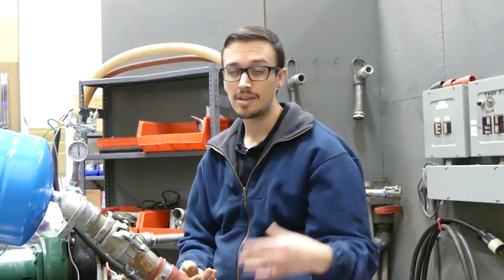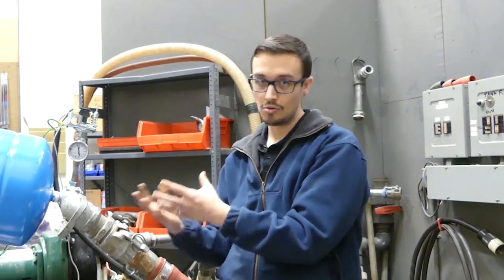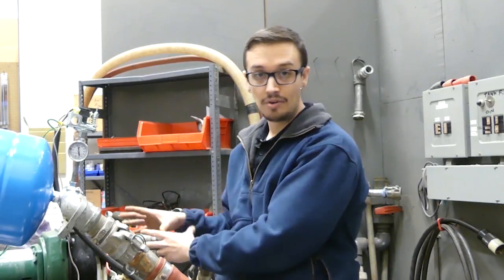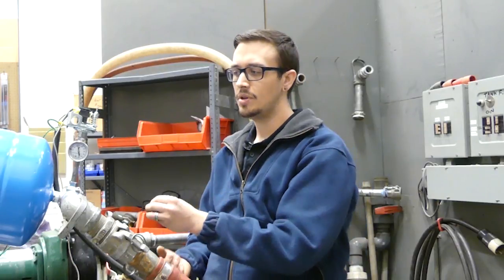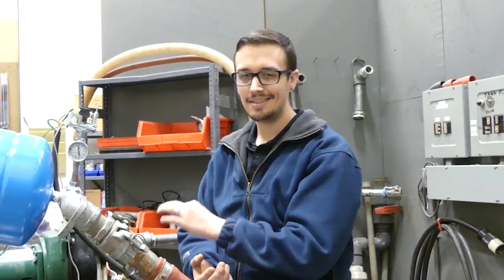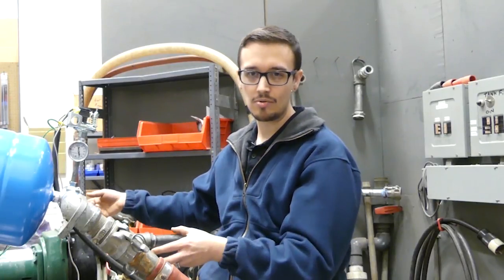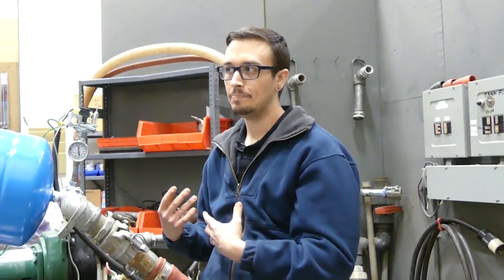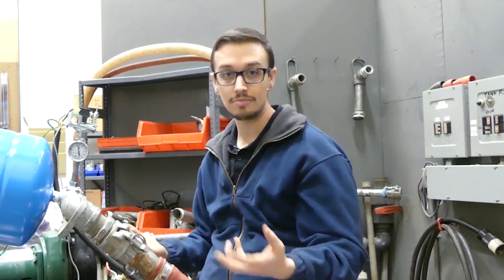That's actually a great question. I don't think it was answered in that other video, but the answer basically is that if the pressure never drops, this switch is just a normal pressure switch. There's not really any circumstance that's going to cause false tripping. The only real thing that could possibly happen, and I haven't tested this, is if you've got a pump that does a lot of volume and a small pressure tank. If you suddenly open up all your taps and that pump is firing on all cylinders, you could potentially have enough pressure loss before the pump kicks on. I think the pump's distance from the pressure switch may play a role in these scenarios. It could have that sudden drop in pressure and cause the switch to trip out on you. I think that's kind of unlikely when you saw how difficult it was for me to get this pump completely unprimed.